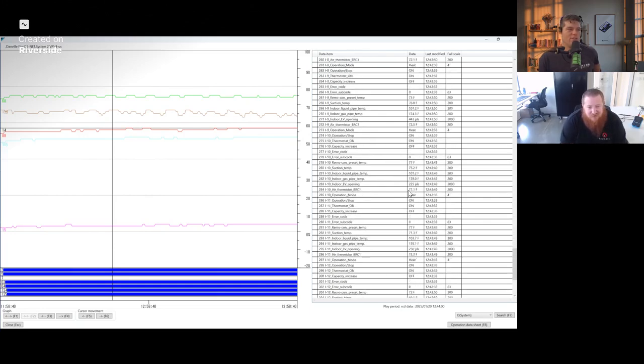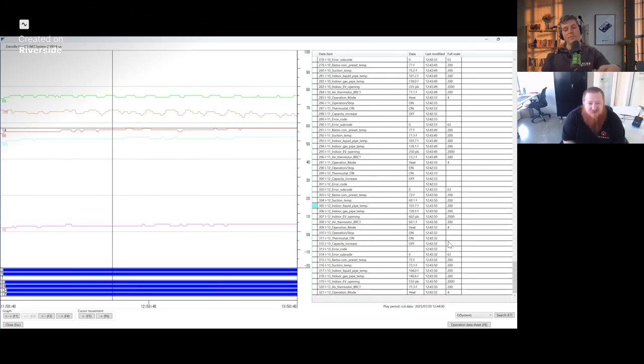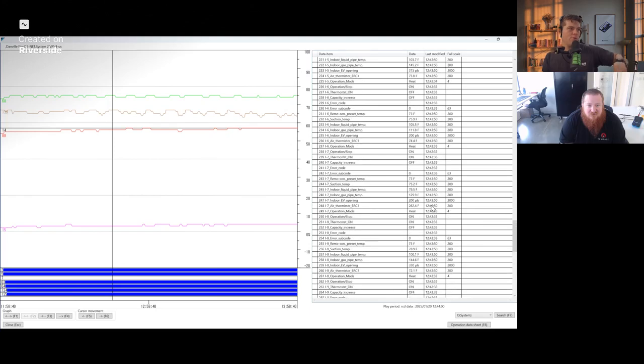Now, this is the part that I love the most. I love to do it this way too. So you do the largest valve pulses, which I love. It's great. There's a lot of ways to skin this cat, this poor cat. I like to find the highest liquid temp, right? So there's 104 here. That one's 137, 103.7. I think 104 is probably going to be the highest.